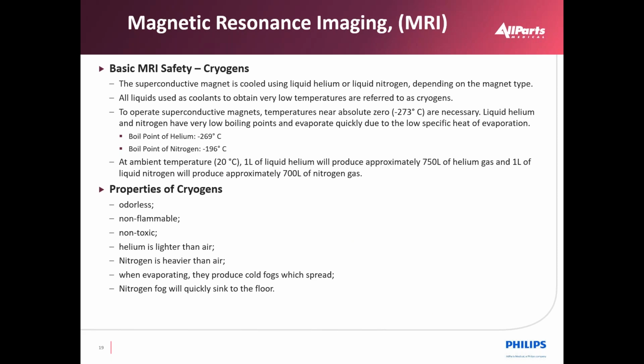Cryogens are used as coolants in the MRI magnet to bring the internal vessel temperature to near absolute zero due to their extremely low temperature characteristics. In older MRI models, liquid nitrogen was used, but in newer, more modern magnets, liquid helium is used to maintain the superconductivity of the MRI magnet. 1 liter of liquid helium will convert to 750 liters of helium gas.